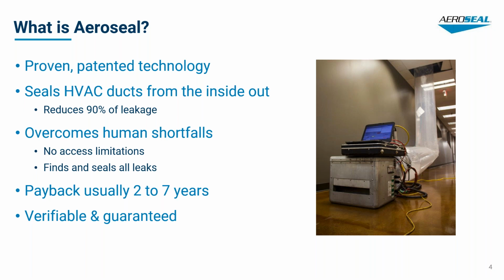We do that sealing by injecting a fog of aerosolized sealant into pressurized ductwork to seal air leaks from the inside. It relies on a software-based system that continuously measures airflow and leakage throughout the sealing process. Water-based sealant particles accumulate only where leaks are located, and it completely closes them off.